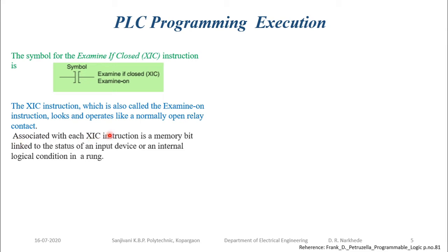Now this XIC instruction, examine if closed, is a single bit and it is related to the status of an input device. Say I have connected a temperature sensor or a limit switch. It will tell me the position, whether the limit switch is activated or not. If I have used a switch, whether the switch is on or off, it will always check the status in the internal memory condition of the rung.